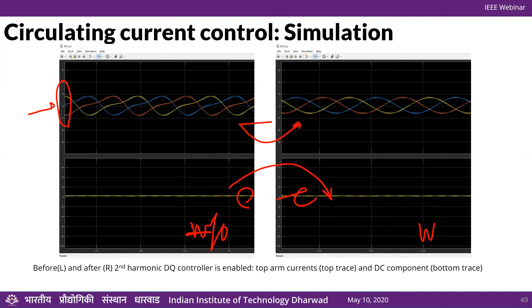Of course, it leads to higher loss and other issues even where current magnitude isn't much affected. What you see on the bottom trace is the average value of all three, the DC component that needs to flow through all three arms. What's important is that this average is unchanged, otherwise our arm energy would go unbalanced. So we want to make sure that doesn't change, only the second harmonic has been eliminated. That's what this slide shows.